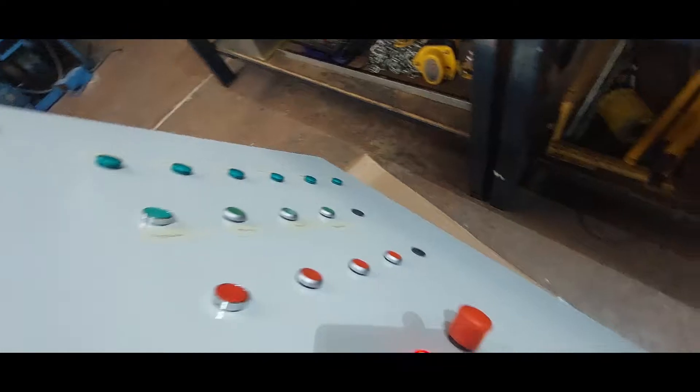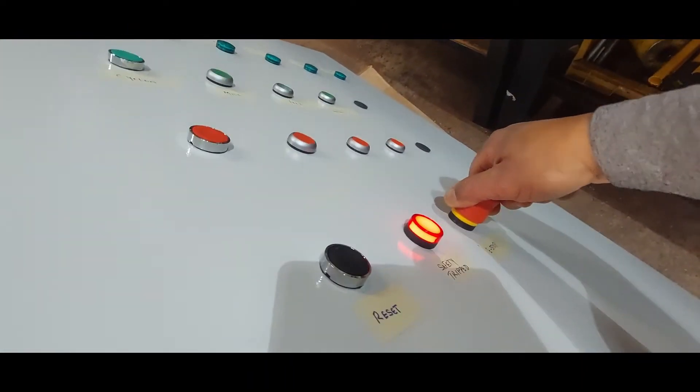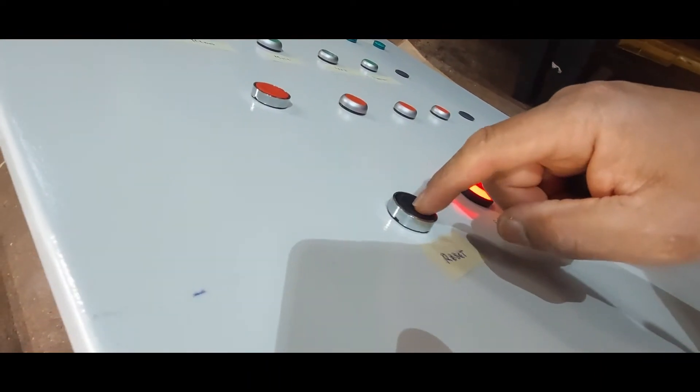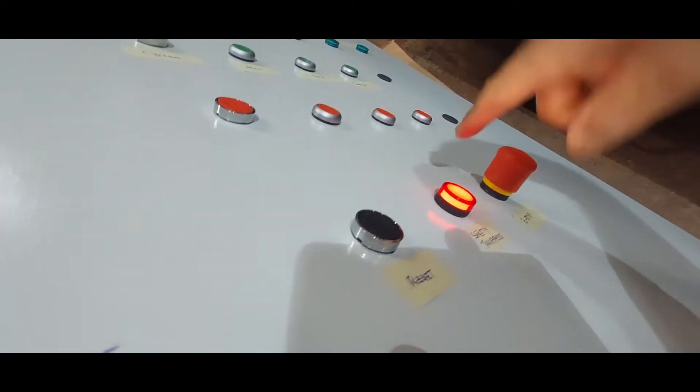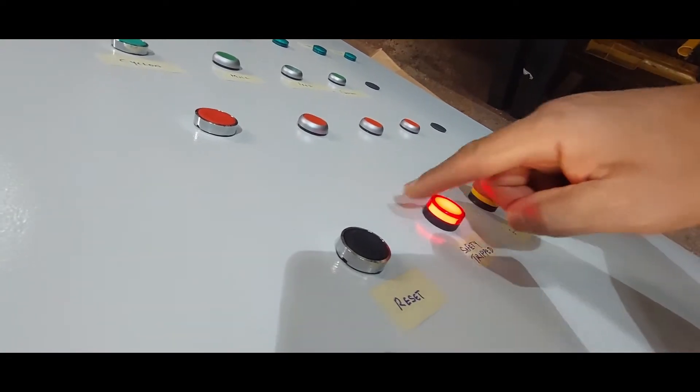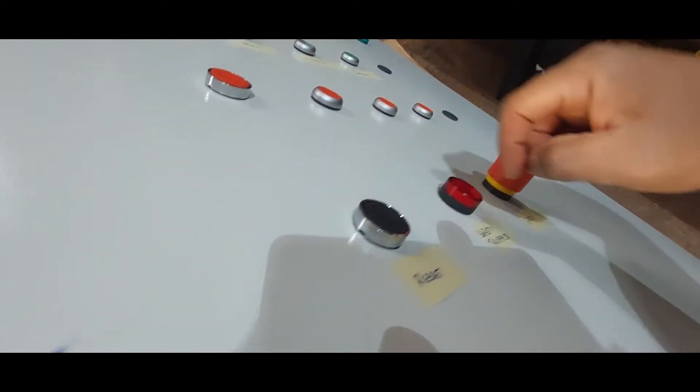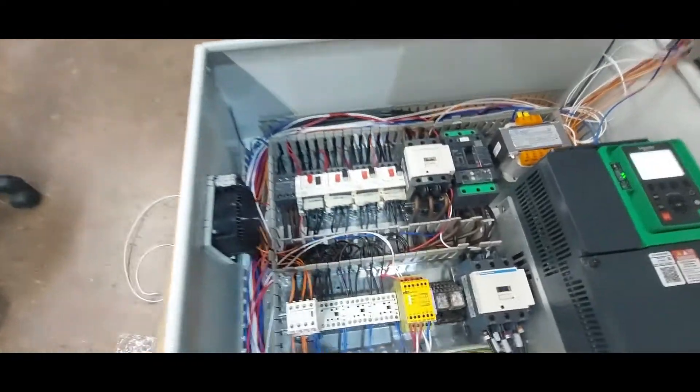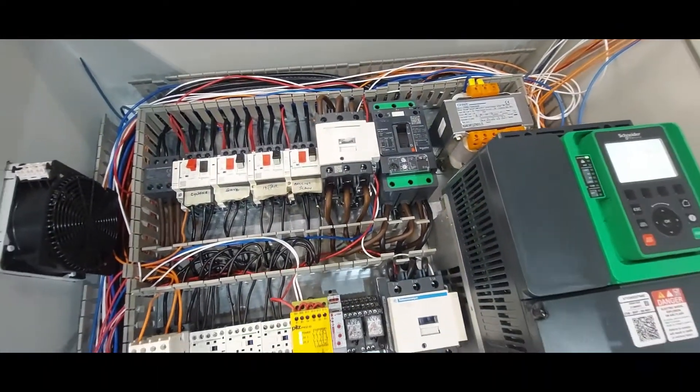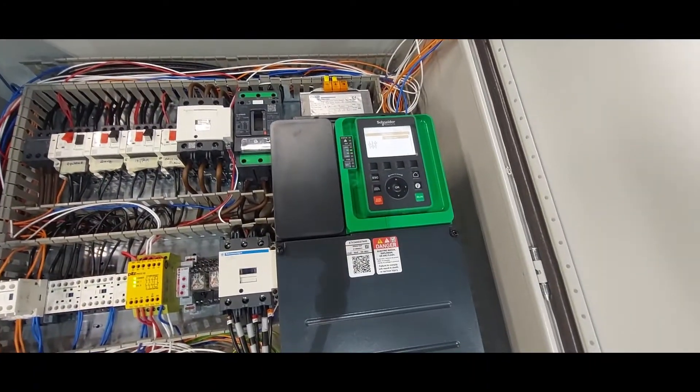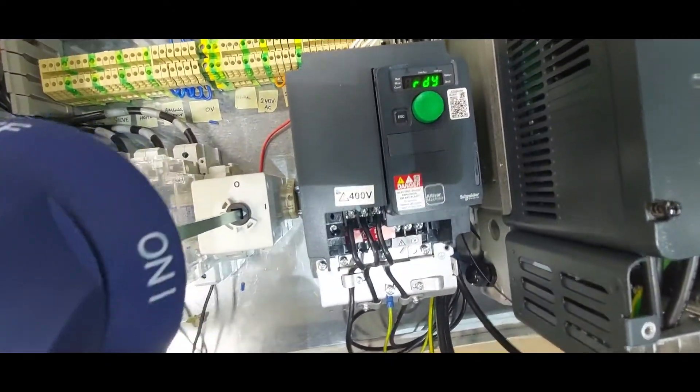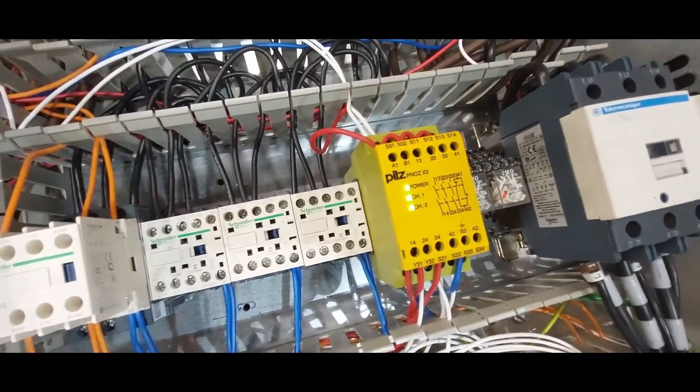So I'm going to remove the E-stop and push the reset button so that this light will disappear. And then the mains contactor has pulled in. You see, the inverter has come alive. This inverter is ready to run and that inverter is ready to run. This is the safety relay, the Pilz safety relay which is governing these two contactors.